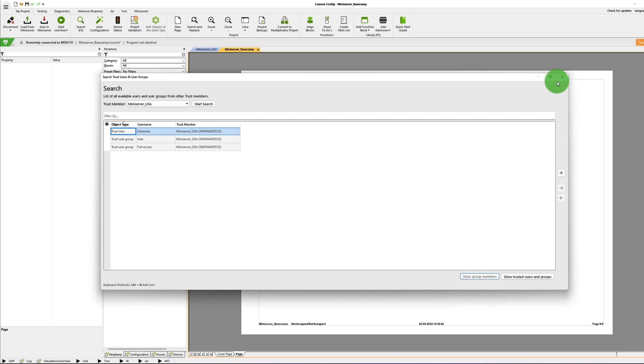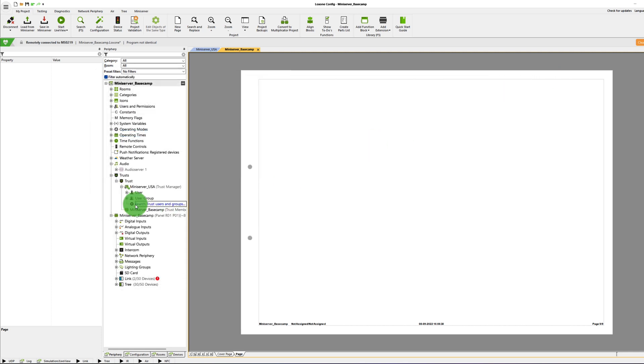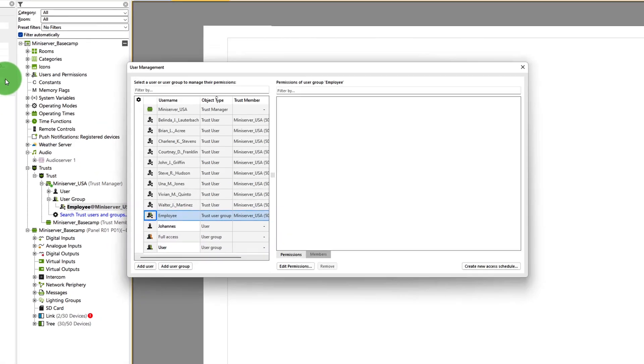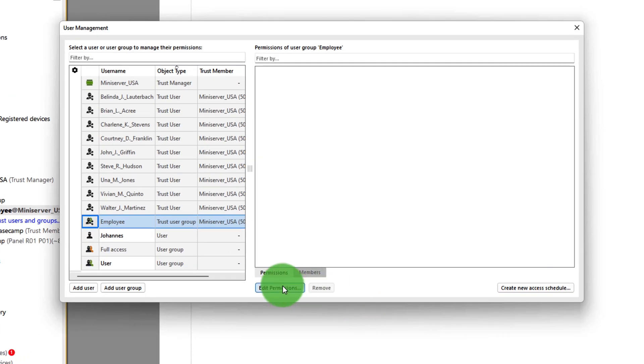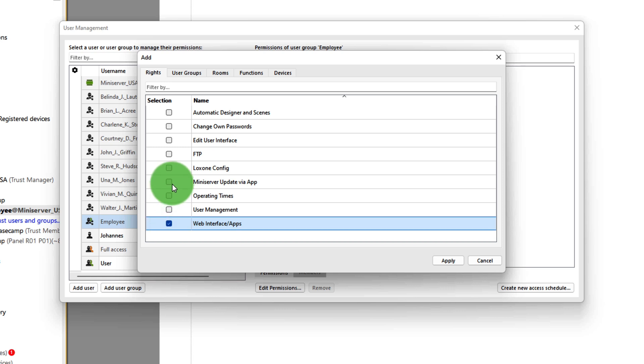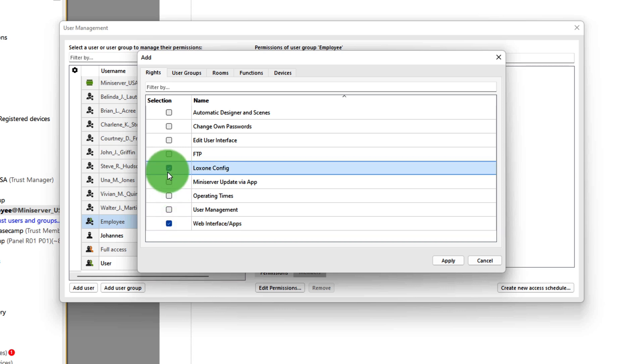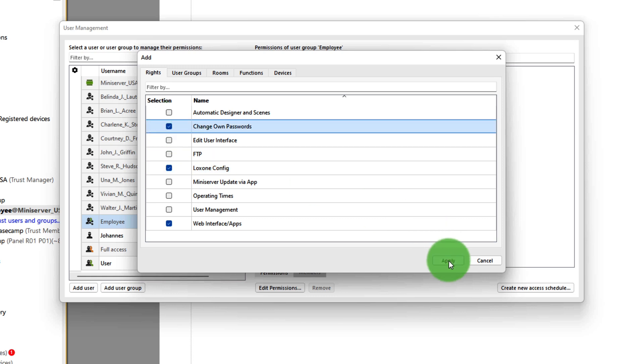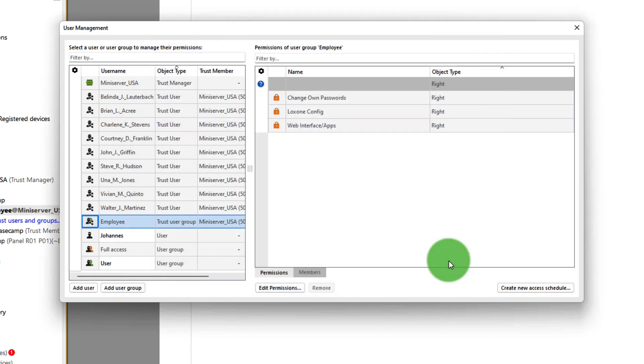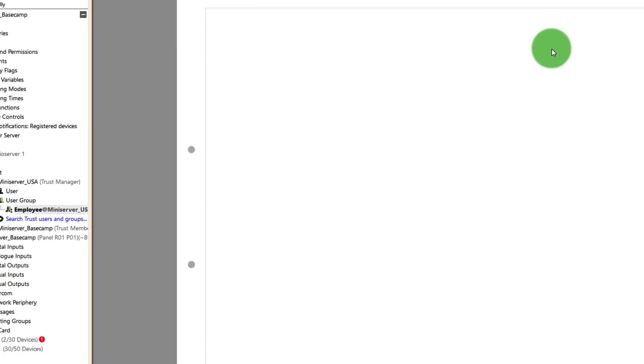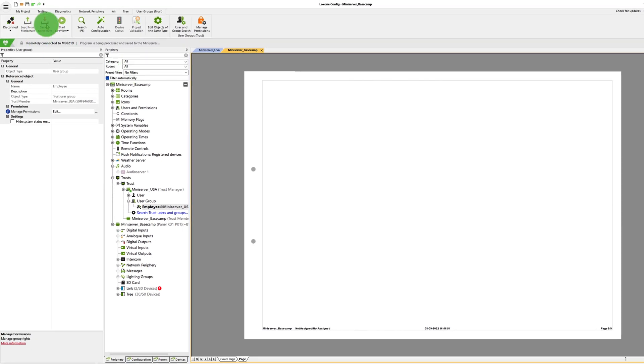The users are transferred along with stored passwords and the signed authentications such as NFC tags and codes. However, the permissions of the users and user groups are not transferred, since these are bound to the mini-server from which the users originate. Therefore, permissions must still be assigned to the newly added users or groups. These are mainly permissions to access the visualization and the authorization for the desired function blocks to allow users or groups to enter the building. Finally, the program must be saved into the mini-server.